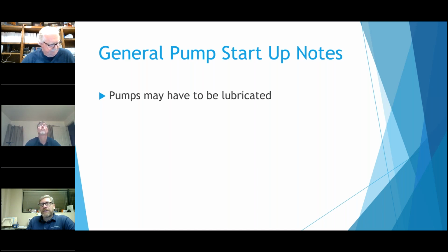It's probably been about 8 years ago, they did change the grease in their pumps. The 1510s used to use the lithium #2 grease. And of course, you don't want to mix the greases between that and Polyrex, which was the other common one that a lot of the motor manufacturers use. But about 8 years ago or so, they changed the grease that they use in the 1510s from the lithium #2 to the Polyrex. So you do want to be careful which grease you're putting in there, because the two evidently shouldn't be mixed together.